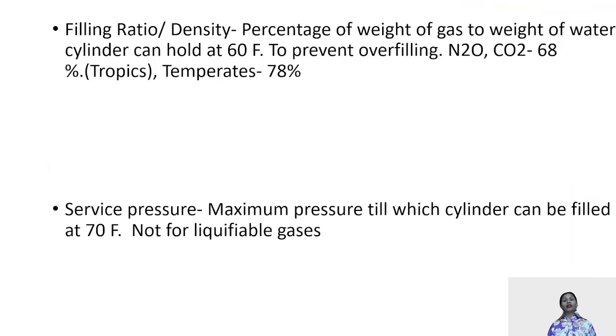Now coming to another very important concept upon filling of the cylinders. When we talk about the non-liquefied gases, they are filled at a pressure known as the service pressure. That is the maximum pressure till which the cylinder can be filled at 70 degree Fahrenheit. And according to the standardization, it is only plus 10% of this filling pressure that the cylinder can be filled.